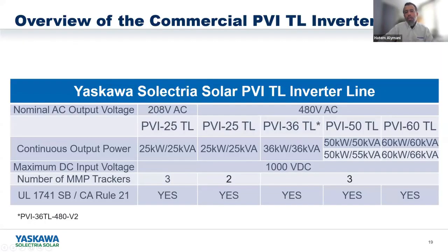Our TL inverters, of course, they are transformerless inverters and they are ungrounded inverters. We have two different output voltages. We have the 25 TL, which is a 208. This is a very, very popular inverter. A lot of different manufacturers kind of shied away from the 208 volt market, but we offer the 25 TL inverter. It has 3 MPPTs and it can take up to 5 strings per MPPT. And we'll talk about that in detail in the future because that's one of the issues that we are noticing with our installers or our customers.